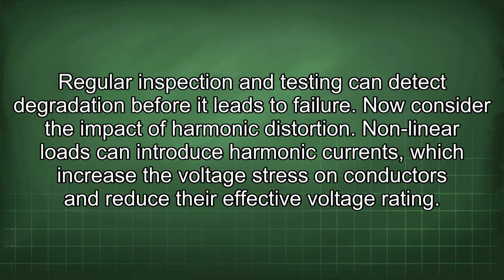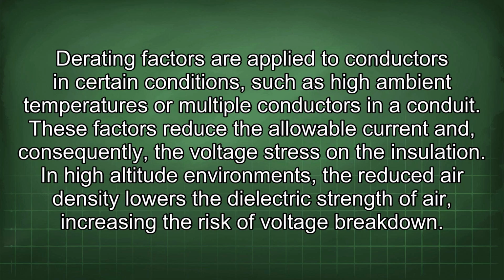Now consider the impact of harmonic distortion. Nonlinear loads can introduce harmonic currents, which increase the voltage stress on conductors and reduce their effective voltage rating. Derating factors are applied to conductors in certain conditions, such as high ambient temperatures or multiple conductors in a conduit.